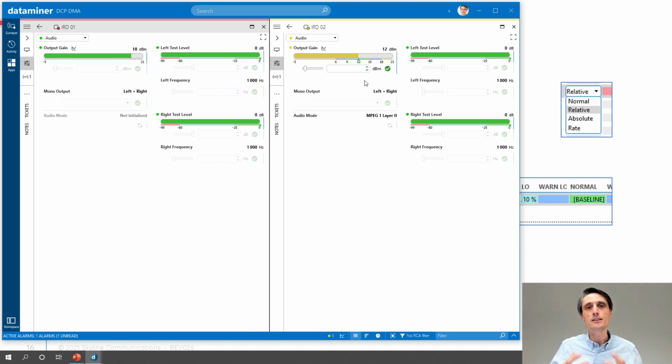But be aware that a rate alarm is by nature an alarm that will automatically disappear. It will be generated, but the next poll cycle, it will be expected to be normal again. If I have a stable value, unless it continuously makes big jumps, then the alarm will remain there. So a small jump now and then, a new error appearing and that number increasing, that's fine.